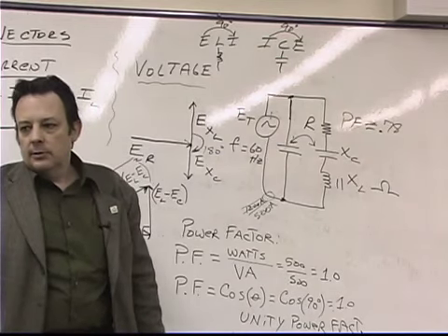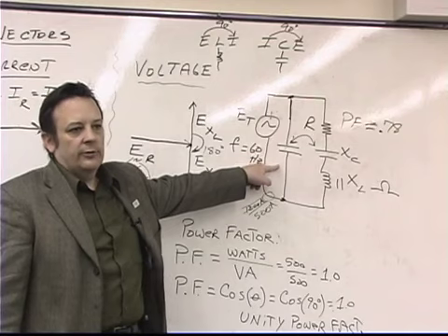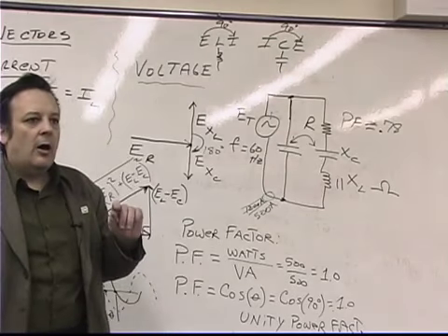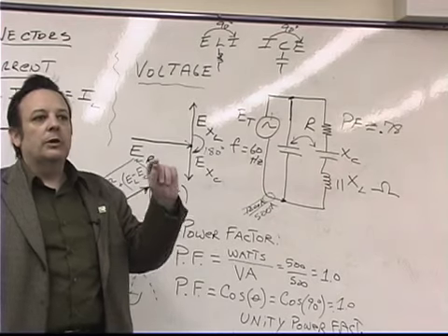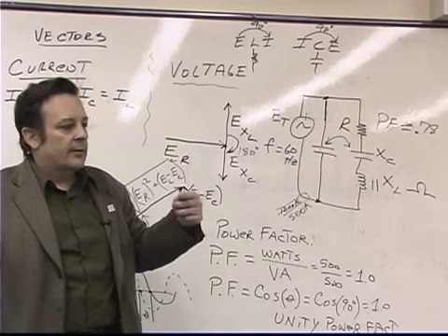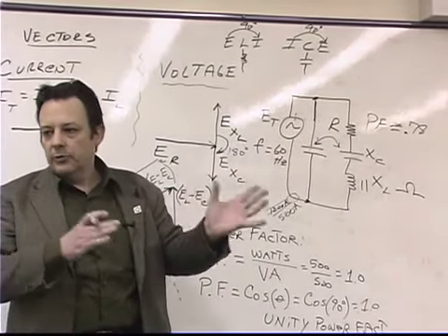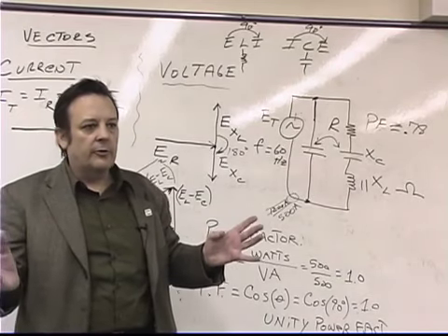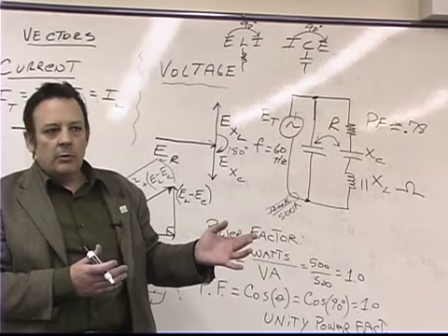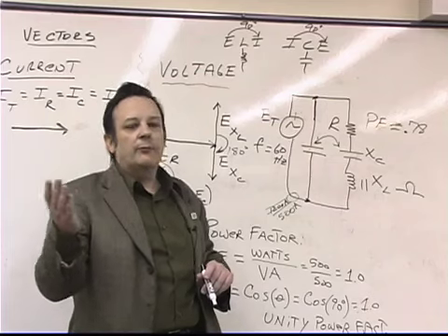Hoorah! The big determination as to whether or not companies will pay for you to do this is what the payback is. What I mean by payback is how long it's going to take the company to recoup its investment in terms of monthly savings. So let's say it's going to cost them $35,000 to put in the capacitor and all of the controls to switch the capacitor with the relays. But let's say we look at their bills and realize it's going to save them $12,000 a month. 12, 24, 36. They paid for their investment in 3 months.